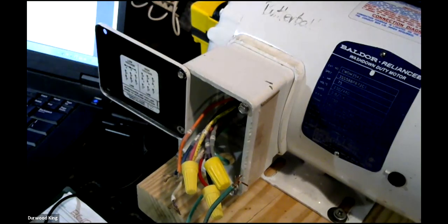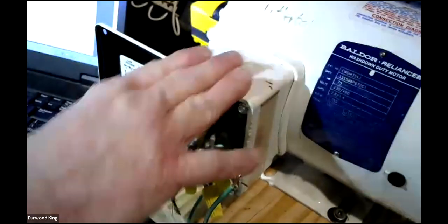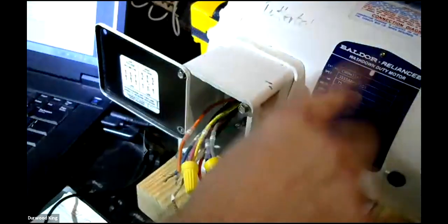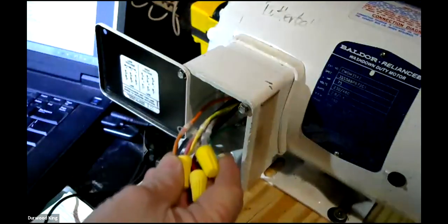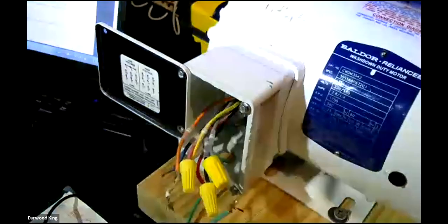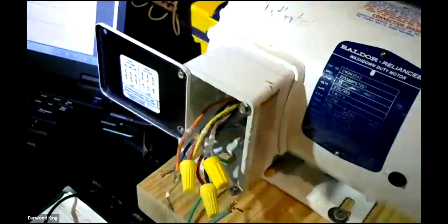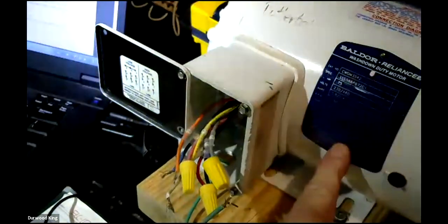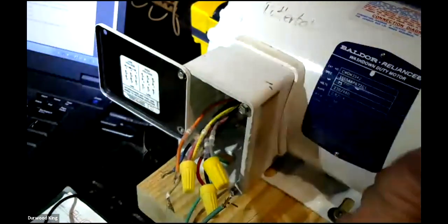That's technically a Y configured motor internally. So inside of the motor here, do you still see my webcam or not? Yeah. Inside that motor, it doesn't tell you on the plate that it's a Y, but there's a way to actually test it with a meter to know if it's a Y. You can pretty much assume if it doesn't say Y, that it is a Y.